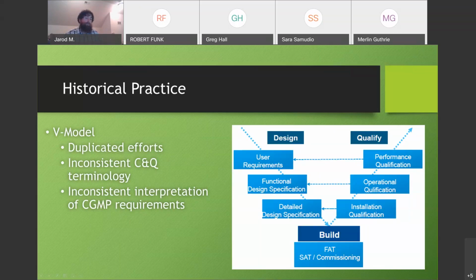Once you have all of those, then you get into the build phase. Within that, you can go back and fine tune and add within the user requirements, and that then feeds into updating your functional specifications and detailed design specifications. That gets into the first part of the commissioning and qualification process, which would be your FAT, or factory acceptance test, heavily reliant on vendor documentation and vendor execution.